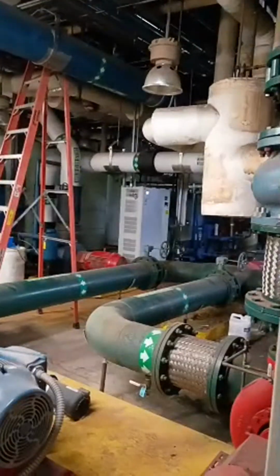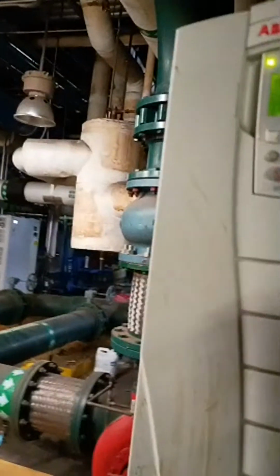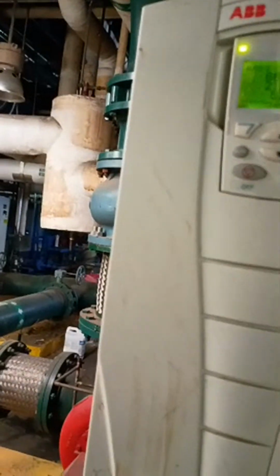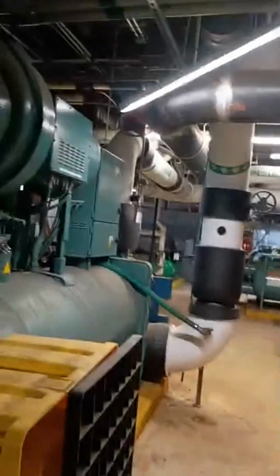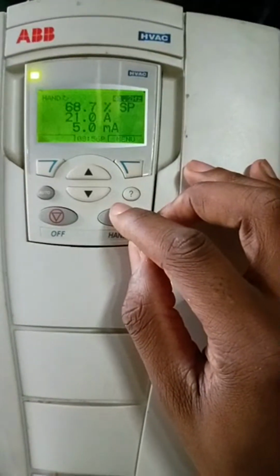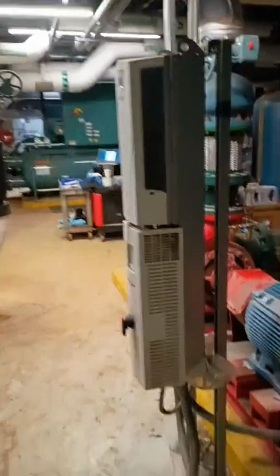Alright, so the pumps are primed, they're pumping water. Before we turn the chiller on, we're going to put them in hand, but bump up their rate so we can change the flow in the chiller. Then when the chiller comes on, it will have enough flow to keep it going. So we're going to put it in hand. We're going to bump this up. And this is for the condenser water. We're going to bump it up just to get the condenser water flowing through this system. We're not going to bump it up too much because it'll suck the water out of the other part of the line, because they're all connected to the same line here. So we're going to get this to 60.